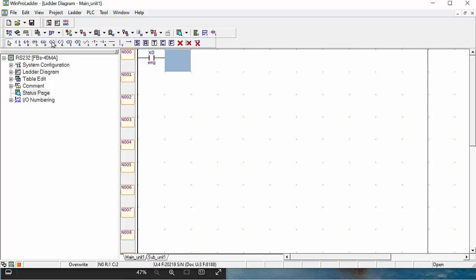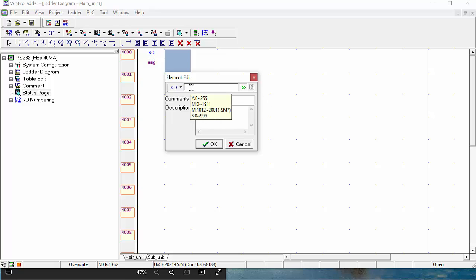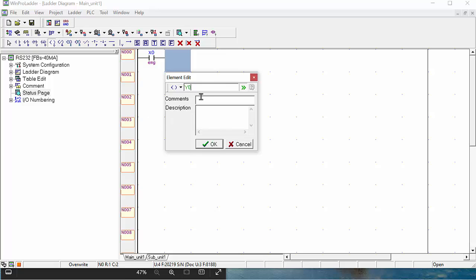Simply your bit is ready in your program. Next, you have to choose the coil. Click here, and it's asking for an address. When you hold your mouse at this area, it shows Y0 to Y255 coils are available in the software. It also shows memory on the down side; I will explain this internal memory later. First, we choose Y0. Y0 is for FATEK PLC output addresses, while X0 defines the input addresses. Here you can give the comment; this is the motor or anything where you can write the name. Then click OK.